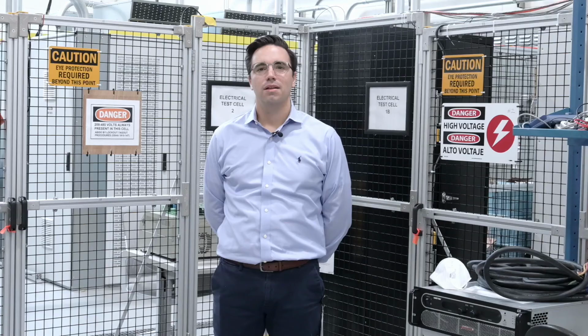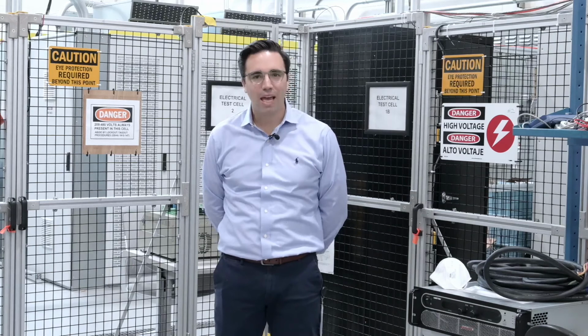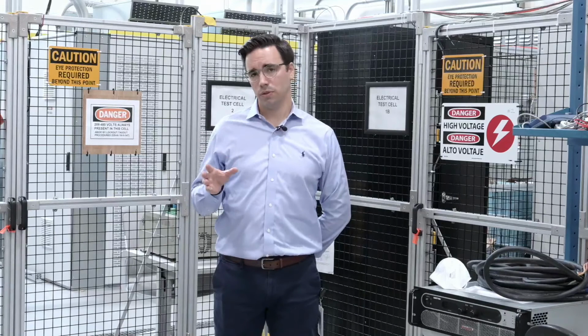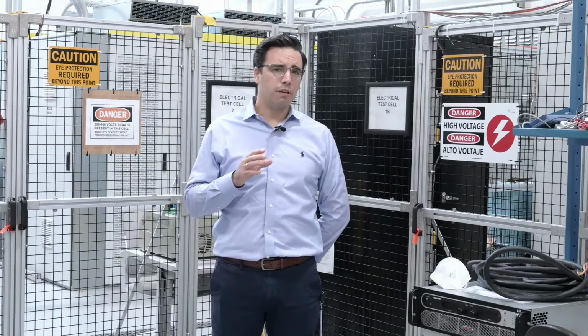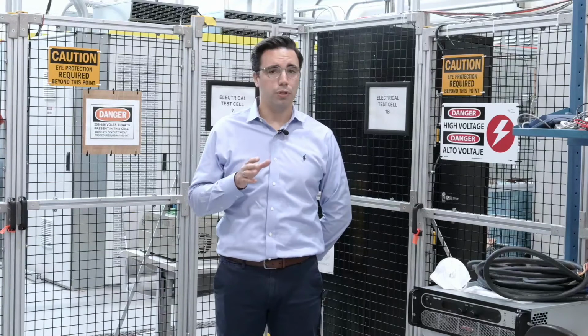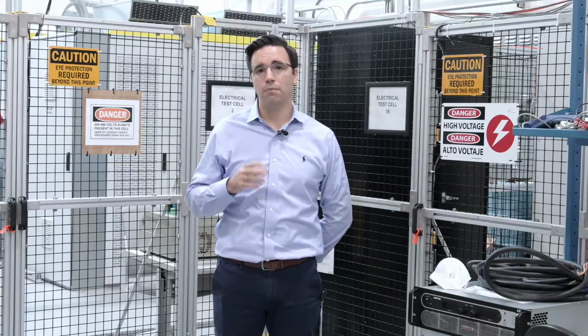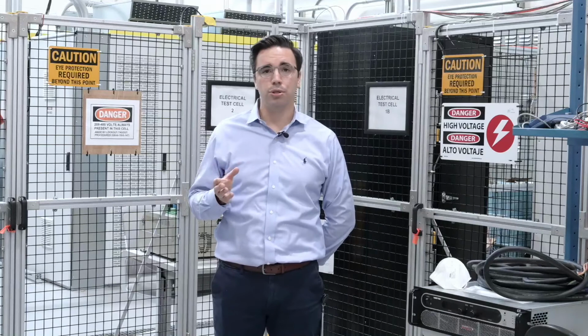Thank you, Marco, and hi, everyone. So when you're looking at a DC distribution system, you have different types of fault scenarios. You have short circuit fault scenarios and ground fault scenarios. Let's start from the short circuits. So in short circuit faults, you expect to have contributions from multiple elements in the system. First, from the main source or the grid through the rectifier. Second, from batteries and battery energy storage connected to the system. And third, the aggregated contributions from all the different EV chargers that are connected to the main distribution bus.